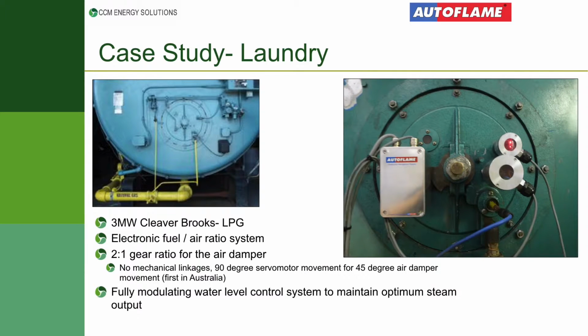We did an installation about 16 months ago at a site, a laundry up in Queensland. This is a Cleaver Brooks boiler. They are common on abattoirs and laundries throughout Australia. The existing burner that you've got here is still very common. This is mechanically driven. You see one modulating motor here, controlling a jack shaft along here, other linkage arms coming down here to control that rotating air damper. Another linkage arm comes down here to control that gas valve. You cannot run that system efficiently.